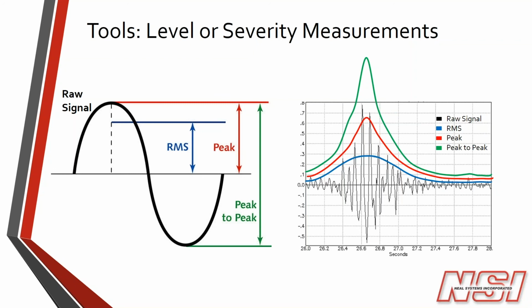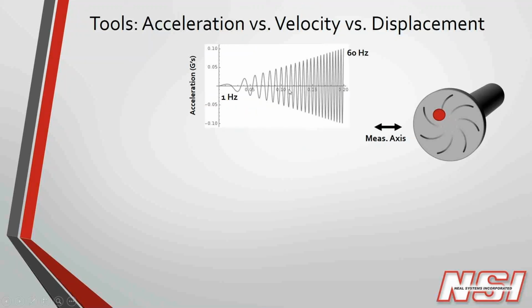And the last one I want to show you is called peak to peak. So when we're measuring displacement, we're typically measuring from the bottom of the negative side of the curve to the top of the positive side of the curve. So over here in this graph on the right, I've shown you an example of some vibration data that increases and decreases. And so you can see the amplitude in RMS, peak, and peak to peak all shown on top of each other just to help you visualize how those signals differ. And you can see how important it is to know in advance what kind of signal you're looking at in order to define the type of severity measurement that you're making.